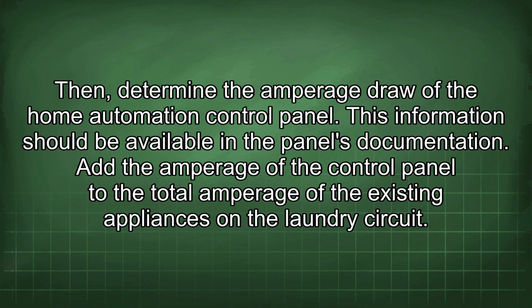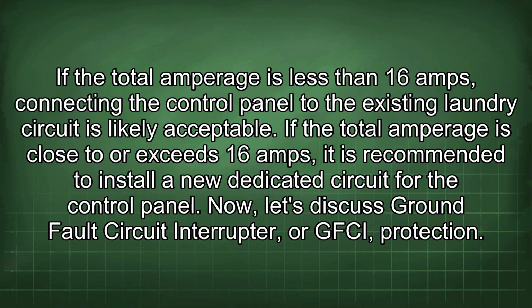Then determine the amperage draw of the home automation control panel. This information should be available in the panel's documentation. Add the amperage of the control panel to the total amperage of the existing appliances on the laundry circuit. If the total amperage is less than 16 amps, connecting the control panel to the existing laundry circuit is likely acceptable. If the total amperage is close to or exceeds 16 amps, it is recommended to install a new dedicated circuit for the control panel.